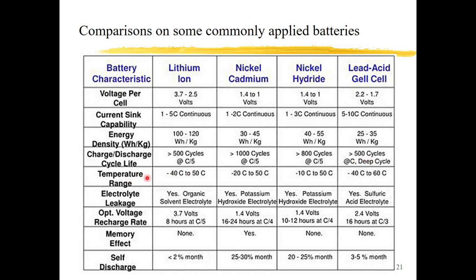And the environment temperature, the battery can be operated within a certain temperature range. Too high a temperature or too low a temperature is not good for the operation of the batteries. For the lithium ion, maybe within this range. For the lead acid, maybe a wider range. But for different designs, they are different. So in this table, you don't have to take the numbers seriously. This is only for reference. We can just compare them, which one is higher, which one is lower. But the number itself, you cannot take too seriously. Okay.